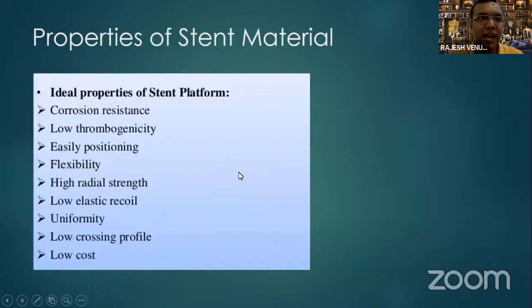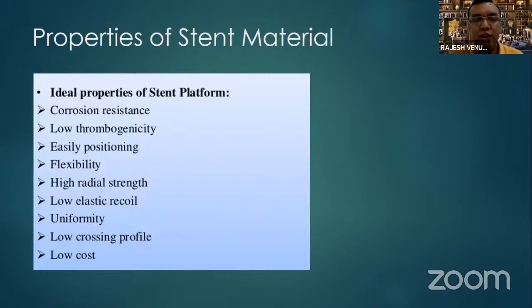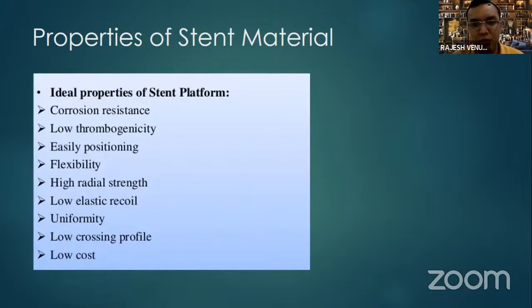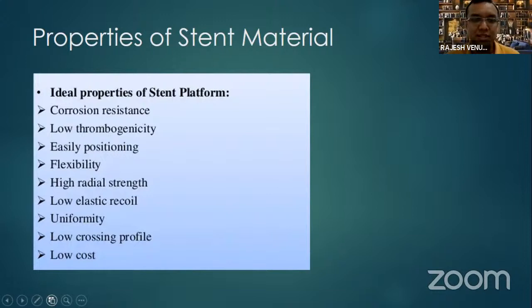The ideal properties of a stent platform are: non-corrosive, low thrombogenicity, easily positionable, high flexibility to negotiate tortuous vessels, high radial strength, low elastic recoil — these last two are most important — uniform caliber with no chance of stenosis, and low crossing profile so the tip is as small as possible. Cost is also a major factor since stents are relatively expensive and mostly imported. In-house manufacturing is considered to reduce costs, as the stent can account for at least one-third of the total procedure cost.